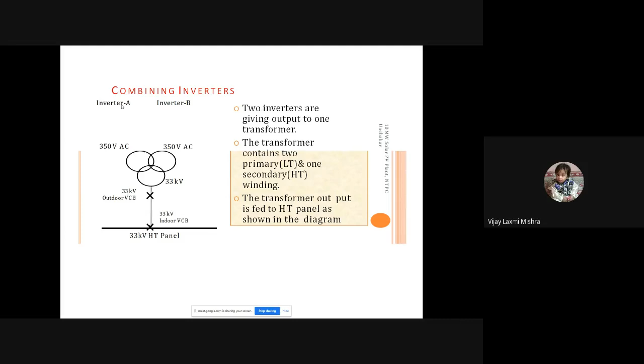In this particular plant there are 16 inverters. Since two inverters are connected to one transformer, there are 8 transformers. These are 16 LT windings, so there is a dual winding arrangement for each of the 8 transformers. This transformer converts 350 volt AC to 33 kV.